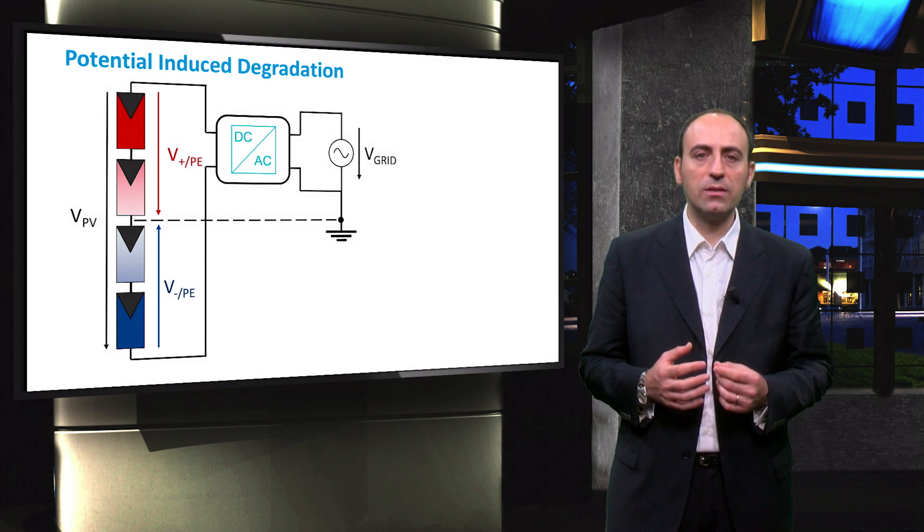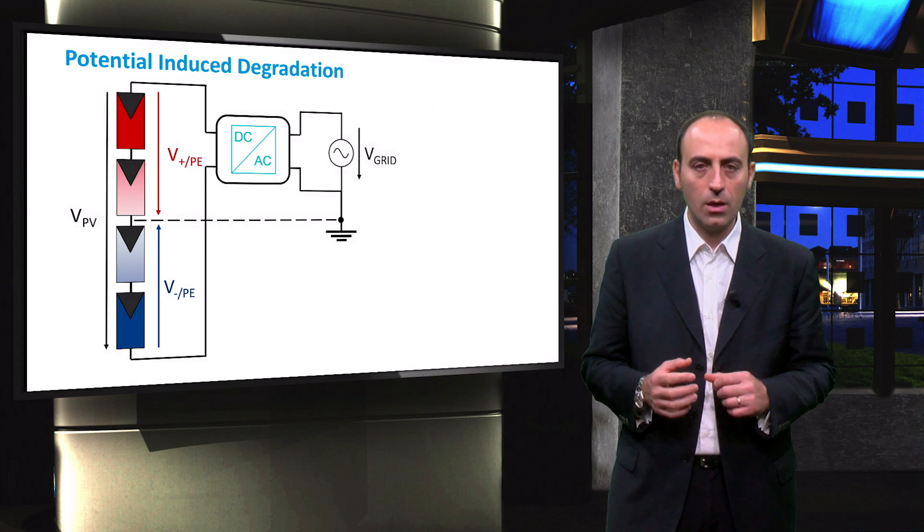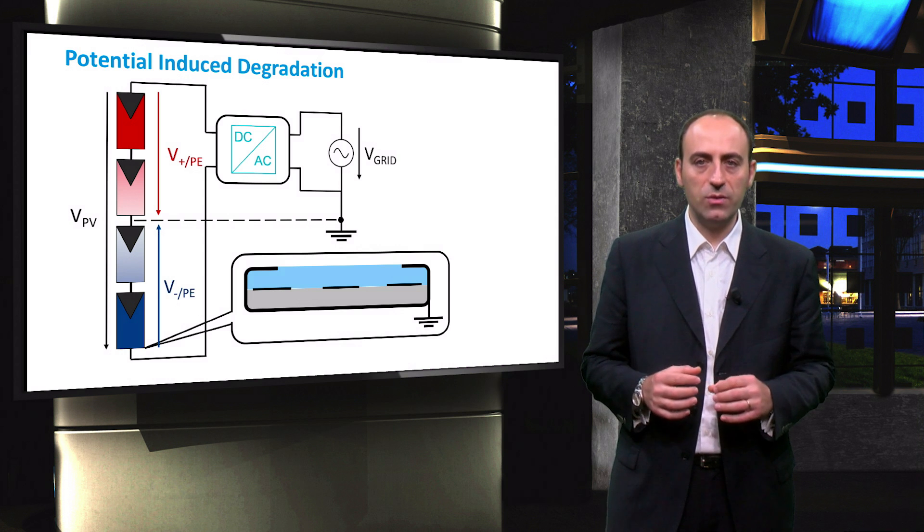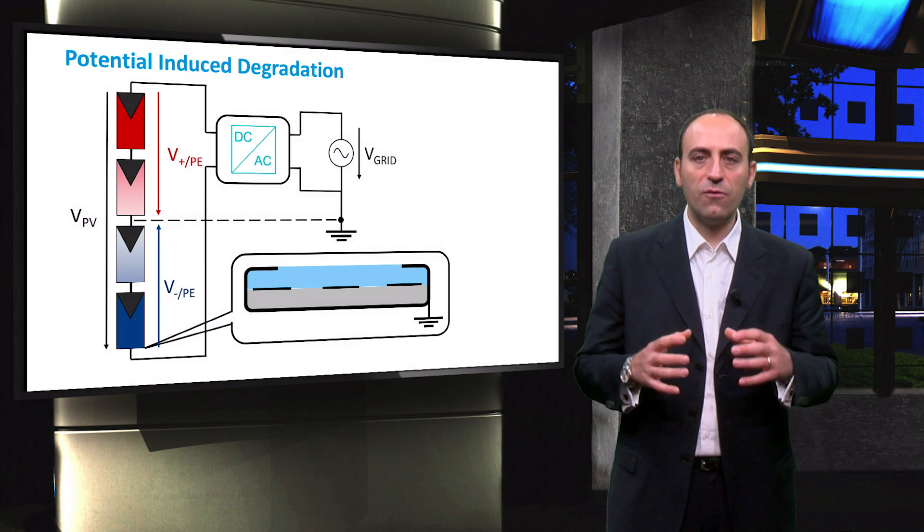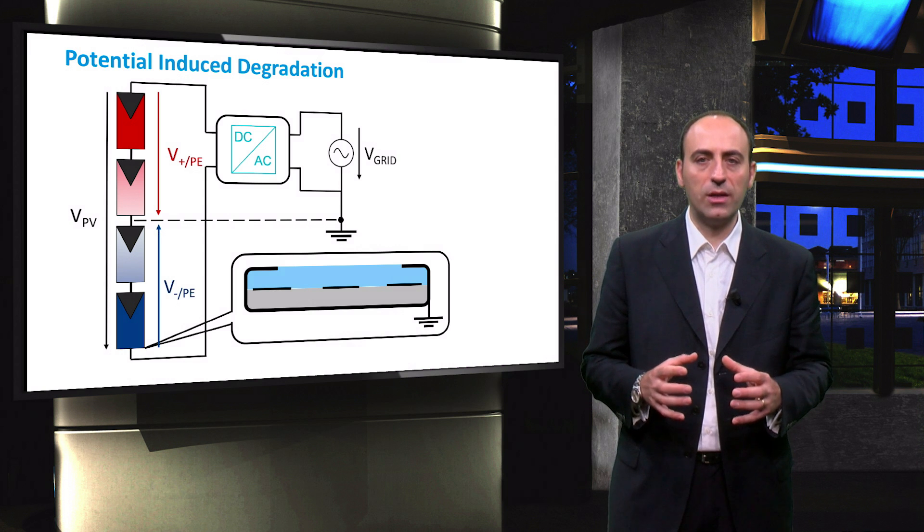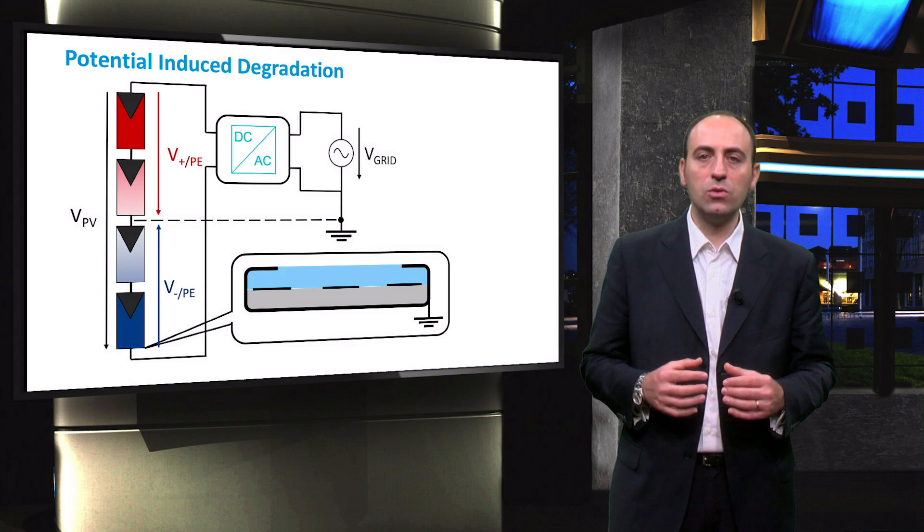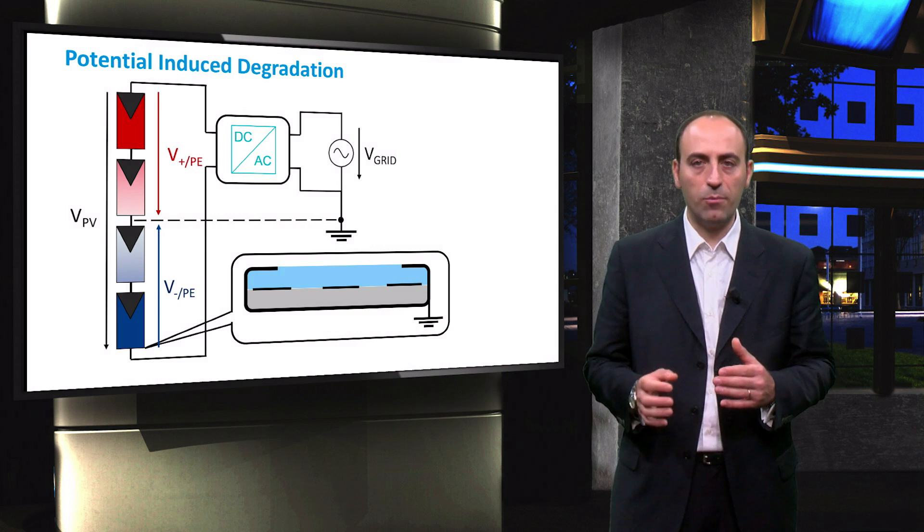depending on the length of the string and the type of the inverter used. The frame of the PV modules must be grounded for safety reasons. This means that the frame always has zero volt potential. Potential induced degradation occurs most commonly in the PV module that is closest to the negative pole.